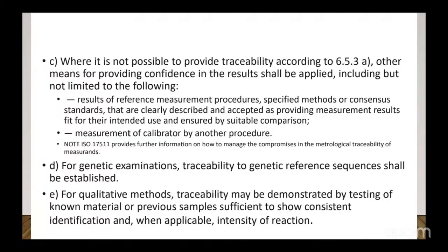Yes. So for qualitative testing, method traceability may be demonstrated by testing known material or previous samples sufficient to consistently identify the result and, when applicable, the intensity of reaction. So here we do measurement traceability.